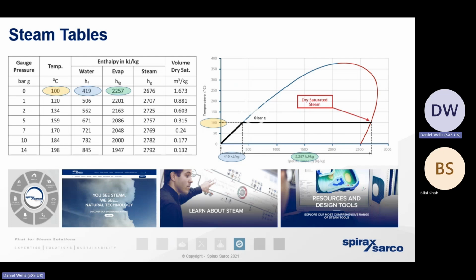So we could be putting 10,000 kilograms of steam into the pipework. We're not going to be getting 10,000 kilograms out at the other side. We might only get, for example, 9,000 kilograms available because 1,000 kilograms of steam is condensing in the pipework. And we've got to get rid of that condensate for reasons we've mentioned, those mechanical issues. So we're going to need to install a greater number of steam traps to drain that condensate away. So that's what we refer to as steam starvation.